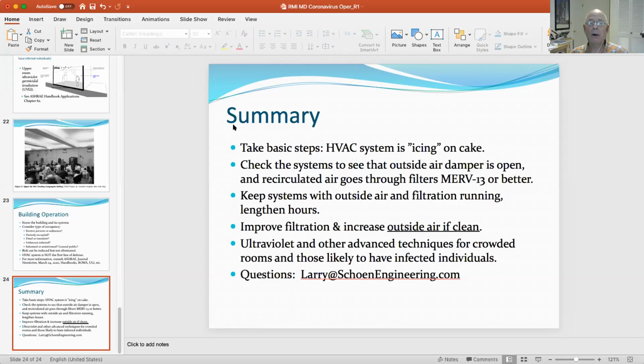And there are mold and moisture issues that can cause sensitized people to have problems. And where does that problem happen? It happens in their respiratory system, the one system in the body that we do not want to compromise at this time. So humidify with great caution in the wintertime. Make sure your maintenance is impeccable and don't go too high in the humidification levels.